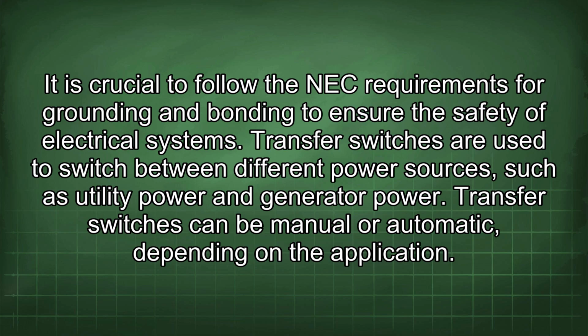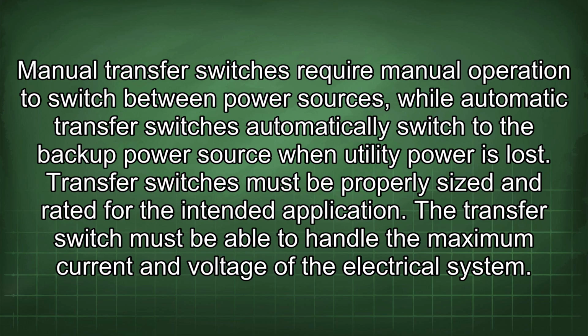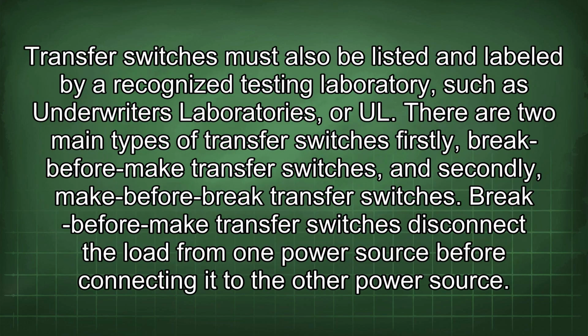Transfer switches are used to switch between different power sources, such as utility power and generator power. Transfer switches can be manual or automatic, depending on the application. Manual transfer switches require manual operation to switch between power sources, while automatic transfer switches automatically switch to the backup power source when utility power is lost. Transfer switches must be properly sized and rated for the intended application. The transfer switch must be able to handle the maximum current and voltage of the electrical system. Transfer switches must also be listed and labeled by a recognized testing laboratory such as Underwriters Laboratories, or UL.